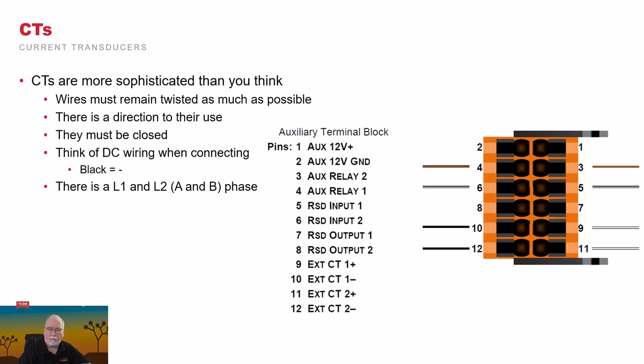CTs are more sophisticated than you think. The wires have to remain twisted as much as possible, and directionality and connection are very important. CTs will have 8-foot leads. They can be extended another 12 to 22 feet for a total of 30-foot maximum with the same gauge cable. Always remember, keep the wires twisted. Make sure that they're wired correctly and installed correctly. These will help you with your self-consumption features.